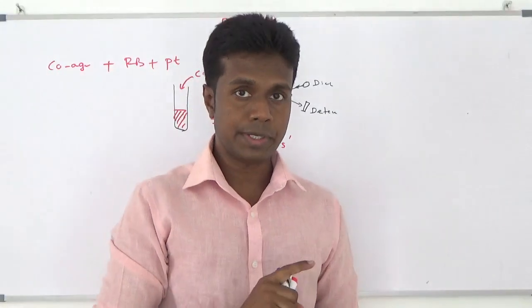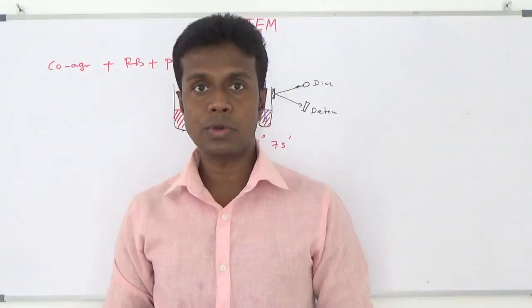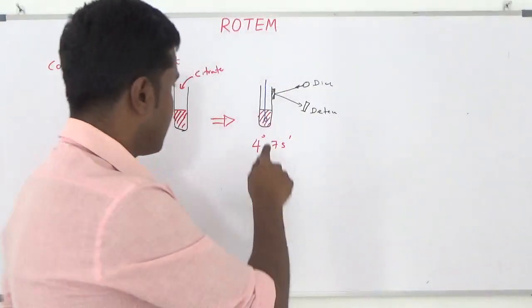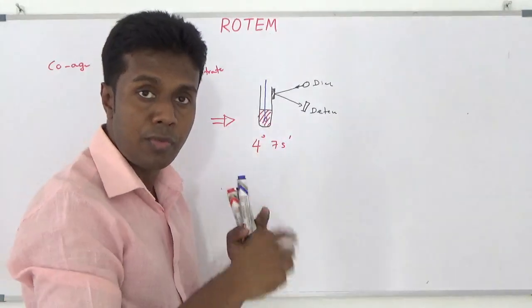With the clot formation, what happened to me is, the rotation ability gradually reduced, because of this viscoelastic property, or during the clot formation, it added a little bit of resistance to my pin. Because of this pin, the rotation ability of my test tube is gradually reduced.